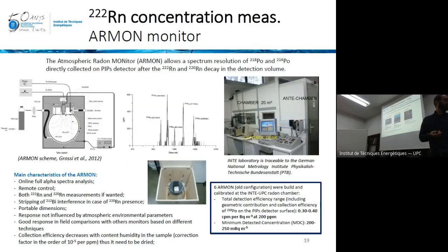This monitor is based on polonium collection at a detector inside a detection ball, inside the sphere, which is charged. This was charged to a few kilovolts. So it is collecting charged particles of polonium, which is a descendant of radon, on the detector.